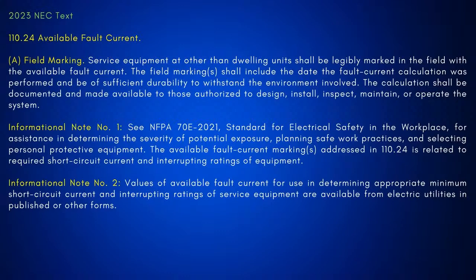That'd be something. Now, if you look here, then you go to 110.24, and what does it say? Available fault current. It says it has to be marked on this and other than dwelling units. It says it'll be legibly marked in the field with the available fault current. And it says those field markings shall include what? The date the fault current calculation was performed, and be of sufficient durability to do what? Withstand the environment once again.